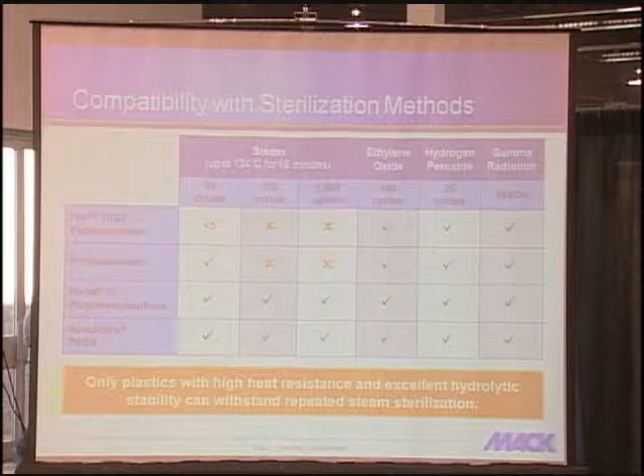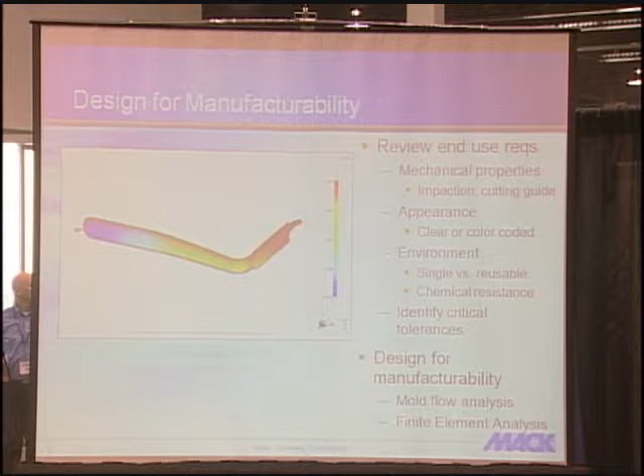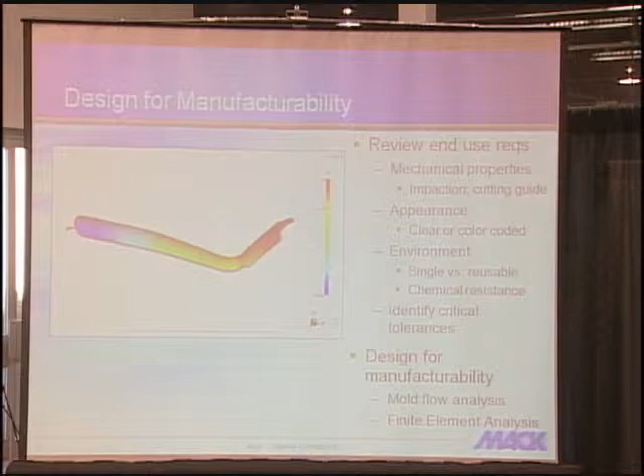So, again, looking at reviewing the end-use requirements of the part, in the environment you're dealing with, if it's single-use or reusable, how does that environment affect the mechanical properties? Is it a part that has to deal with impaction forces or wear behavior? Is the appearance going to change over time with repeated sterilization cycles? How do those repeat cycles deal with critical tolerances for dimensionally tight components? And then looking at how you're going to, can you actually make the part? Can you design the plastic part to be manufactured? And we look at things like mold flow and FEA analysis to determine if the part can perform equivalent to a metal component.